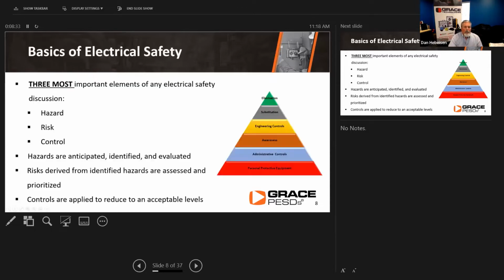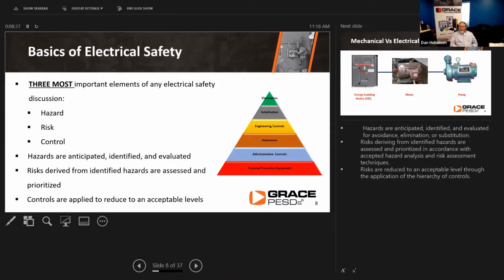So real quickly, this has come up frequently, and really the three most important elements of an electrical safety discussion are the hazard, the risk, and then the control. And I know the majority of people on this call today have seen the risk control hierarchy before and are familiar with it, that the best activities take place at the elimination of risk. If we can create an environment where we are able to eliminate the risk, and we reduce the amount of incident energy that's available, or eliminate the exposure, that's obviously a best practice and is the most effective. If there's a way where we can substitute that risk, can we change the current system? Can we go to a faster fuse?